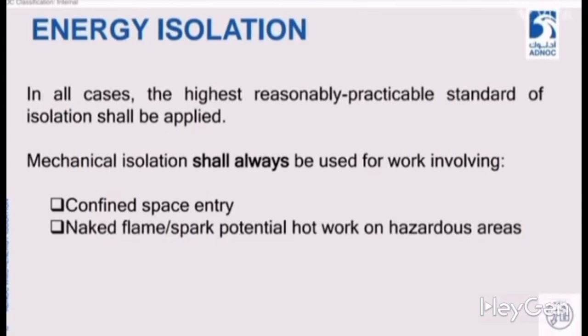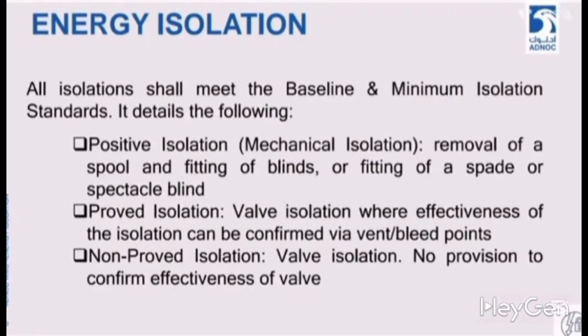We will do a second layer of isolation, for flame, spark, potential ignition. We have to do it in a hazardous area: block, stop, isolate, double isolation. With isolation, we will ensure our work can be executed safely. We need to block, stop and isolate the source of energy or any ignition source. We will ensure mechanical isolation, double isolation and positive isolation. Any energy isolation must achieve or meet the baseline or minimum isolation standards.